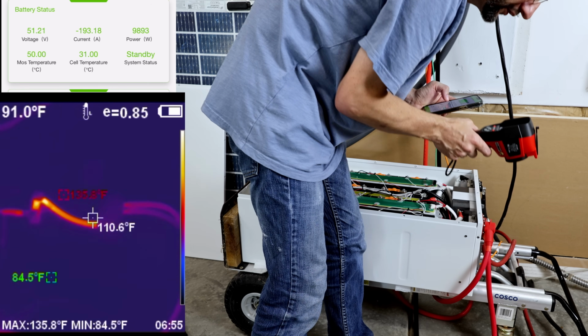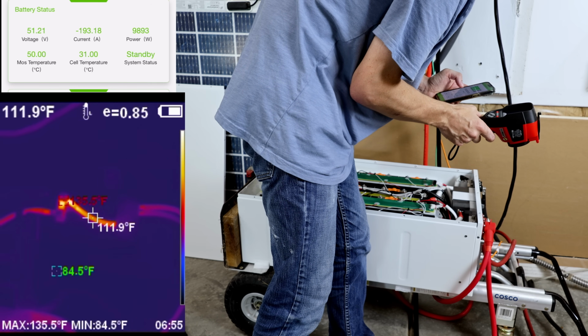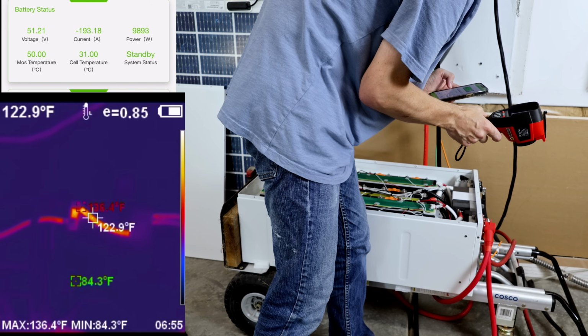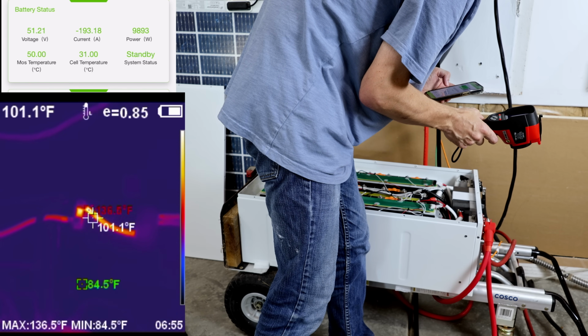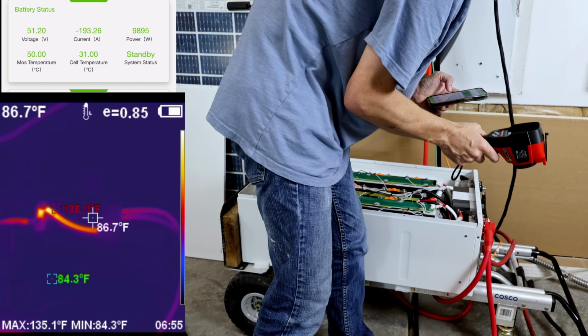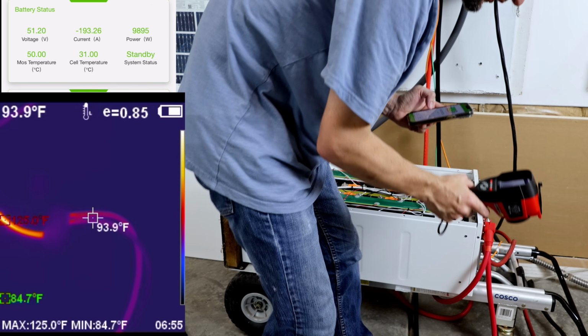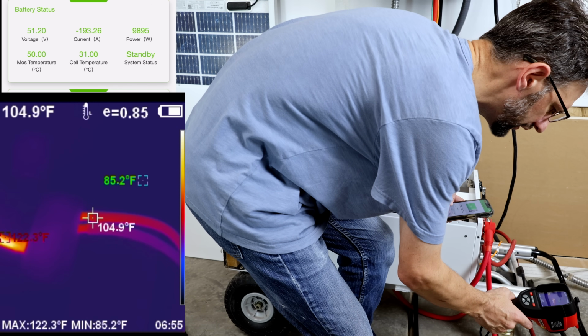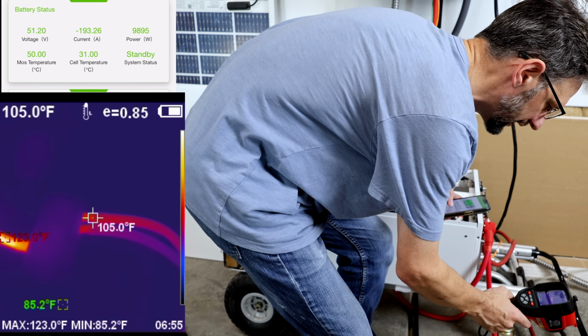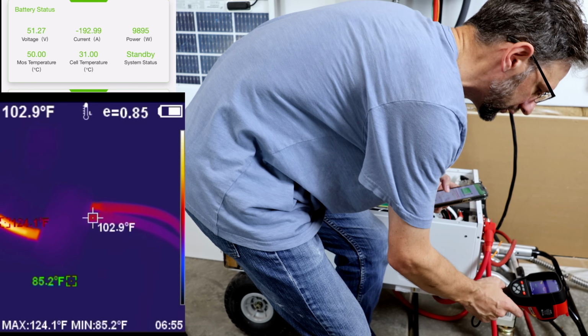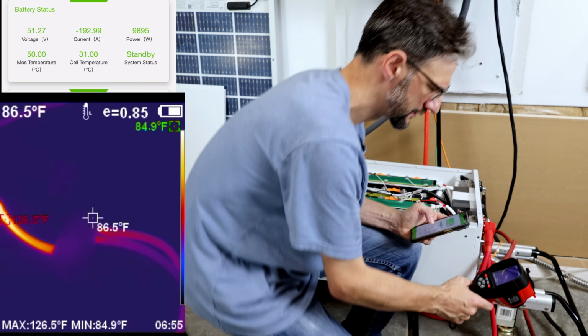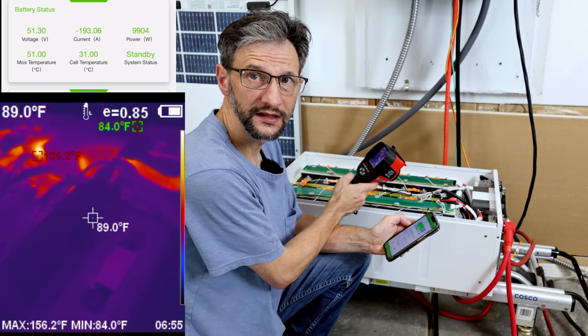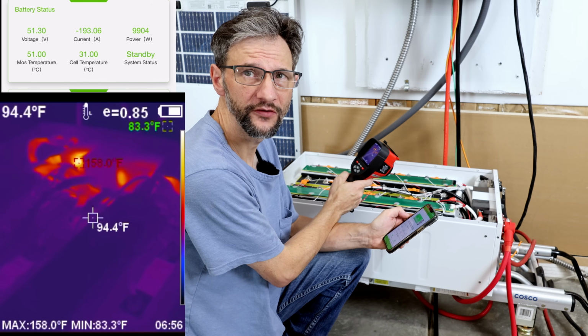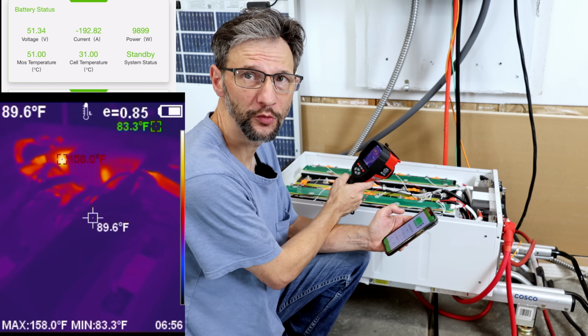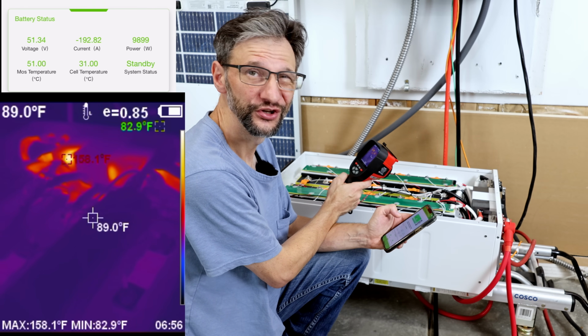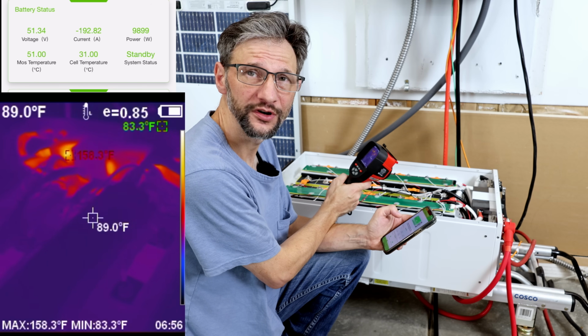Now you can see the difference here in these cables. The cable carrying 10,000 watts is about 130 degrees. And then it's split off into the two inverters there. The hotter one, just over 100 degrees, is probably carrying 8,000 watts, and then that cooler one's carrying 2,000 watts. Well, that gives you a pretty good idea of what this battery can do. If you have an 8,000 watt inverter, one battery should be no problem. If you have a 10,000 watt inverter, you're going to be bouncing against the limit. You might want to get two batteries.